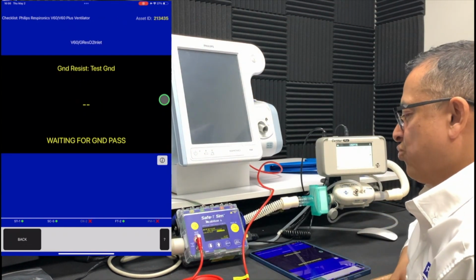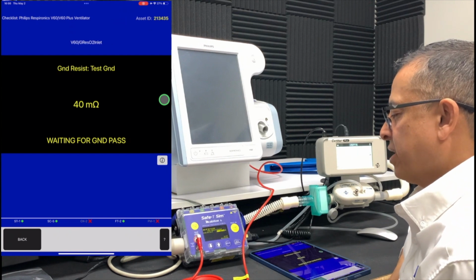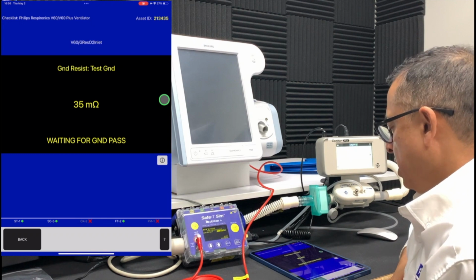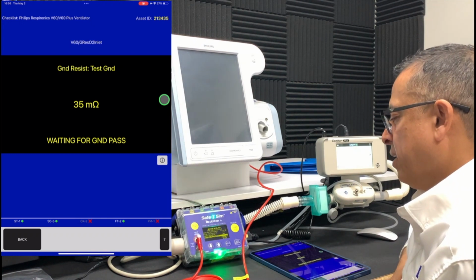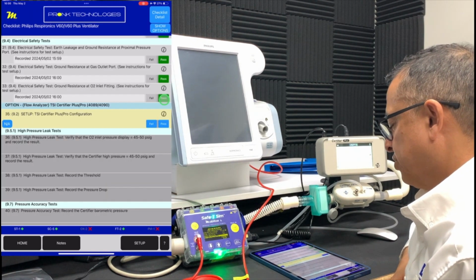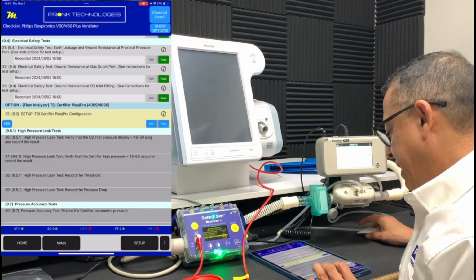And we'll get that last reading to make sure it's within the limits. Our limit here needs to be within 200 milliohms. So in this case, we're well within that limit. We've completed those 3 electrical safety tests. So we can go on to the next test.